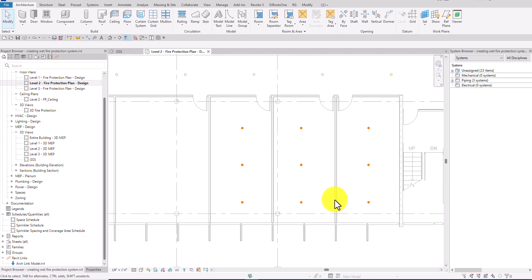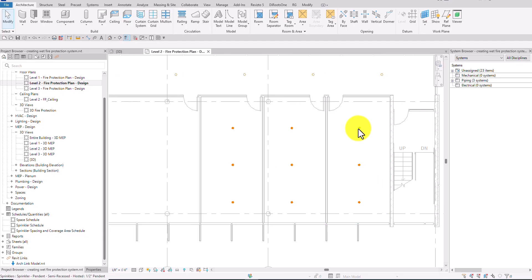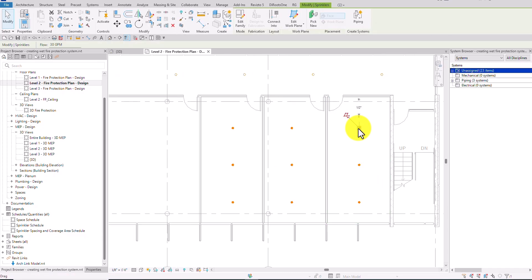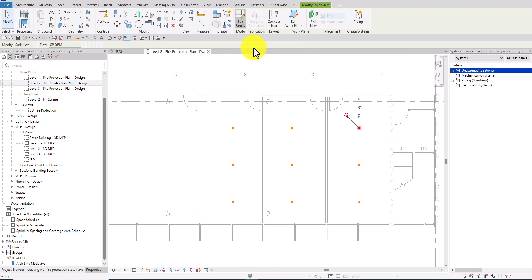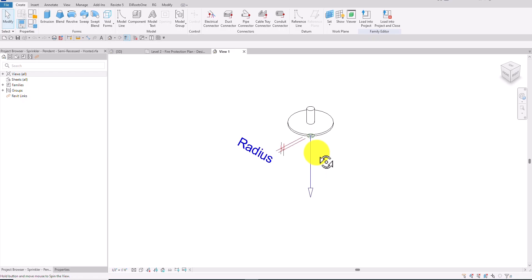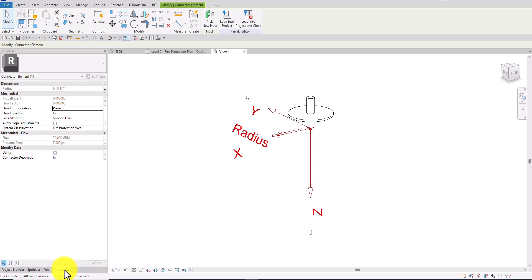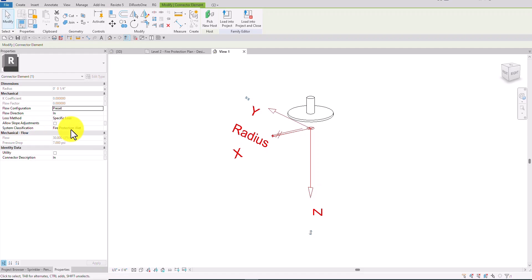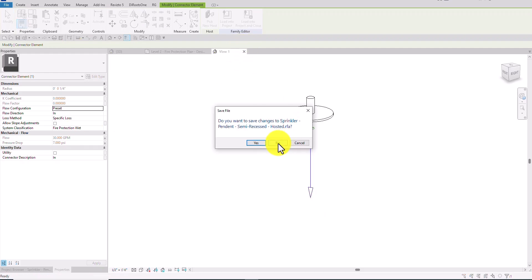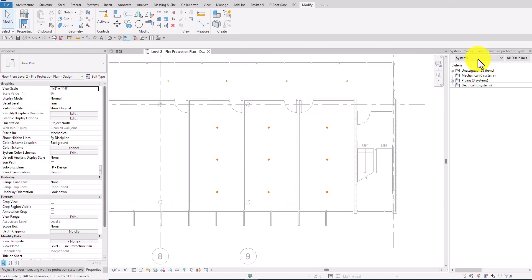The sprinklers I have placed in these three spaces are hosted family. If I click one of the sprinklers and then select Edit Family, I can see there is a connector. If I click that connector and check the properties, the system classification is fire protection wet. That's why the fire protection system we'll be creating from this sprinkler is fire protection wet.